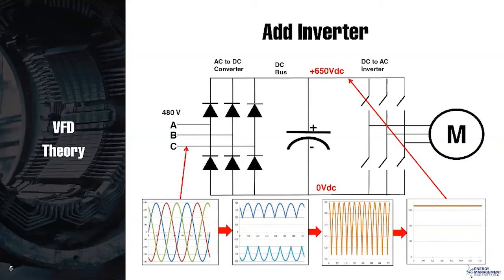Now, if you have your standard voltmeter, you can measure between P, the positive bus, and that top motor lead, and you can test that one IGBT. You test it exactly the same as you do the diodes. And so with 12 tests, you can test each one of the IGBTs, see if that IGBT is open or shorted. Let's go to the next slide.